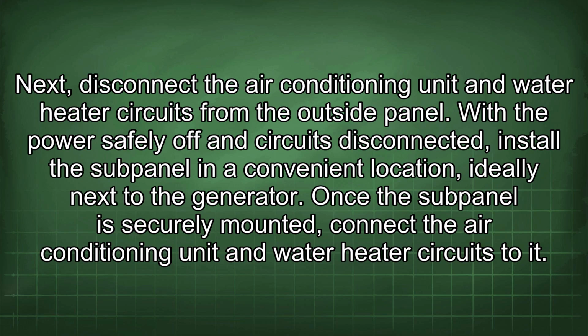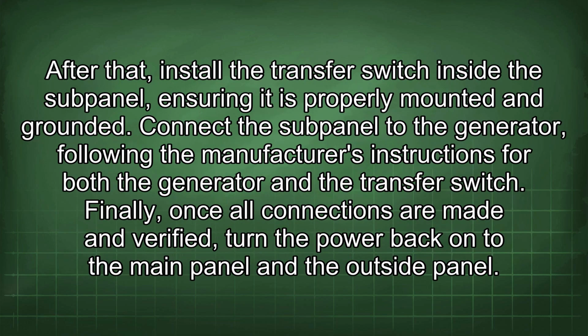Once the subpanel is securely mounted, connect the air conditioning unit and water heater circuits to it. After that, install the transfer switch inside the subpanel, ensuring it is properly mounted and grounded. Connect the subpanel to the generator, following the manufacturer's instructions for both the generator and the transfer switch. Finally, once all connections are made and verified, turn the power back onto the main panel and the outside panel.